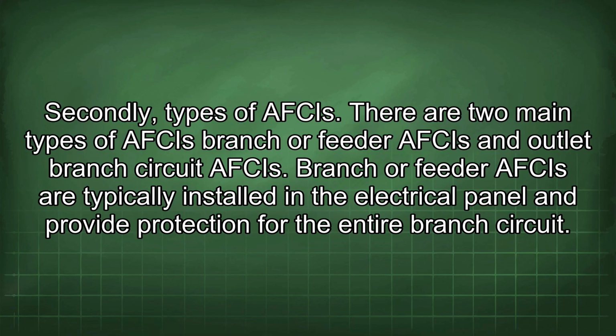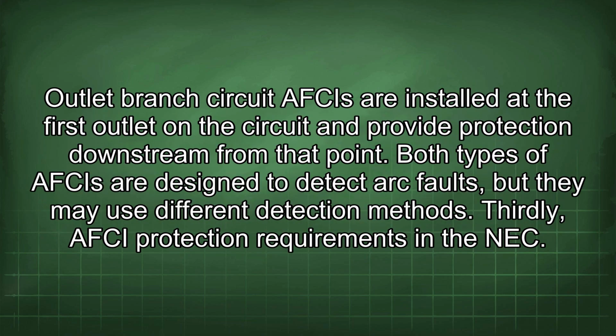There are two main types of AFCIs: branch or feeder AFCIs and outlet branch circuit AFCIs. Branch or feeder AFCIs are typically installed in the electrical panel and provide protection for the entire branch circuit. Outlet branch circuit AFCIs are installed at the first outlet on the circuit and provide protection downstream from that point. Both types of AFCIs are designed to detect arc faults, but they may use different detection methods. Thirdly, AFCI protection requirements in the NEC.